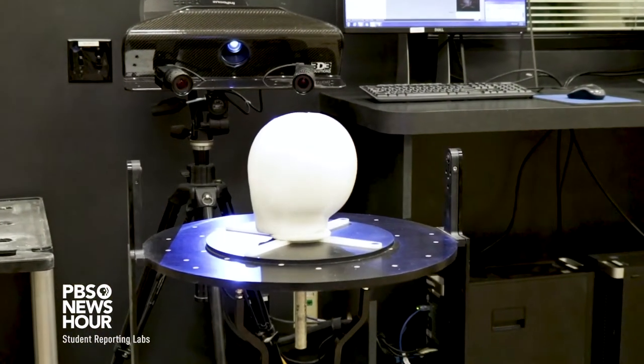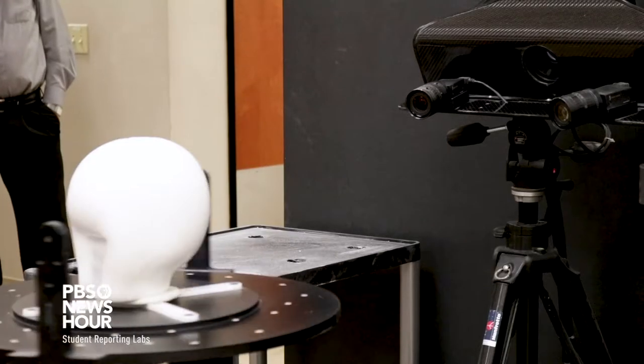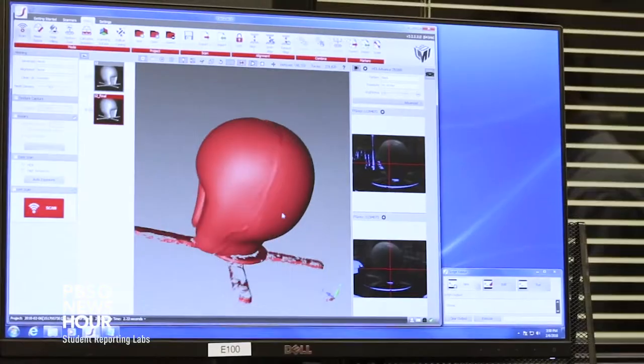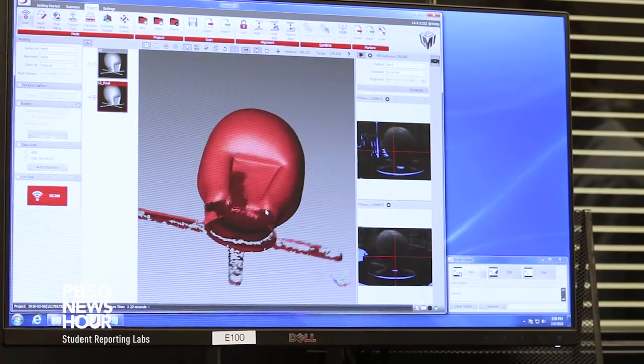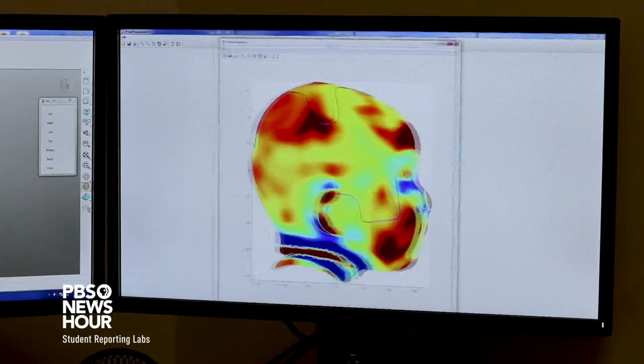Cranial Technologies has invented several technologies, like DSI scanning. DSI stands for digital surface imaging, and that was a technology we developed specifically for children with plagiocephaly. It uses a number of triangulated cameras that instantaneously take a picture of a baby sitting in the system, and within just a fraction of a second, we obtain a full three-dimensional model of the child's head shape, including a photographic overlay morphed onto the surface. That's the image we use to actually make the medical device.